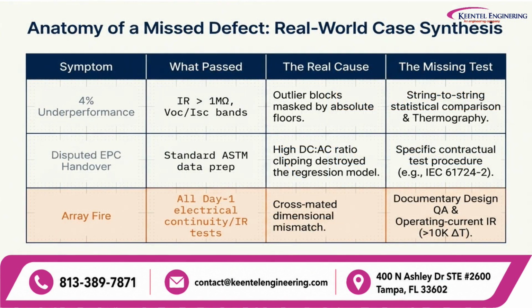Synthesizing real-world asset failures reveals a clear pattern. 4% power deficits frequently trace back to outlier blocks that passed static 1 megaohm floors, which could have been identified using string-level statistical comparisons and thermography. Handover disputes consistently stem from using unadjusted ASTM models on highly clipped systems, and catastrophic array fires inevitably occur after cross-mated connectors pass day one electrical tests. In every instance, conventional compliance gave a false sense of security, where advanced commissioning would have resolved the risk.